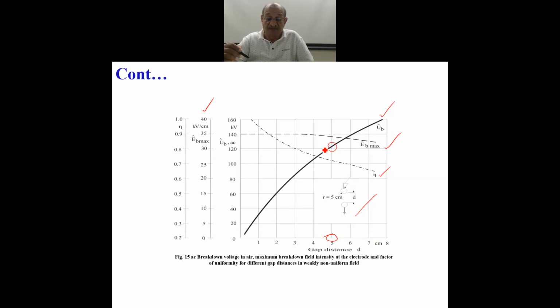So you can say the field remains under weakly non-uniform configuration up to a gap distance equal to the radius of the sphere. This is a very important conclusion. Based on this conclusion, in the earlier days, when voltage measurement techniques were not very developed, people used to have two spheres for measurement of the voltage, and the only way to estimate the voltage applied was when a breakdown was created. The breakdown characteristic, as you see, is linearly proportional. It is a straight line up to this gap distance. So this was used very widely for the measurement of high voltages of all types. There are tables available. We'll come to it a little later.